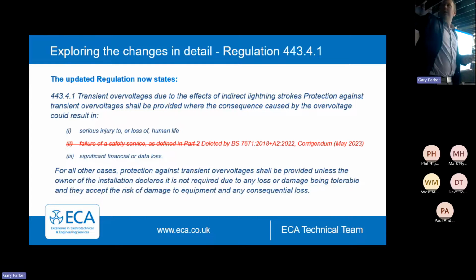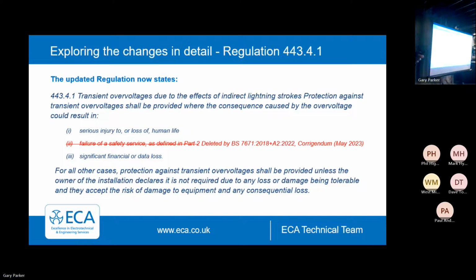Well, actually, that's okay if you've got an SPD there, but what if the surge comes in over there? It's got to go through my router before it gets to my distribution board if it comes through the data cable. If it comes through the aerial, it's going to have to hit my telly first before it gets to my distribution board. It offers me no benefit in that sense.